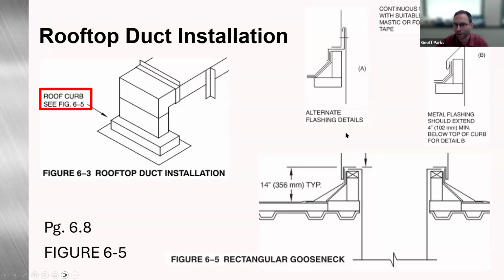There's some alternate flashing details, A and B. Metal flashing should extend 4-inch minimum below the top of the roof curb for detail B. So that, and the architectural sheet metal manual has many more types of flashing and curb details than we do in the HVAC duct construction standards. But this is what's covered in the standard.